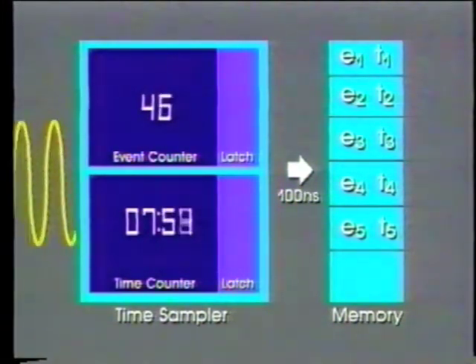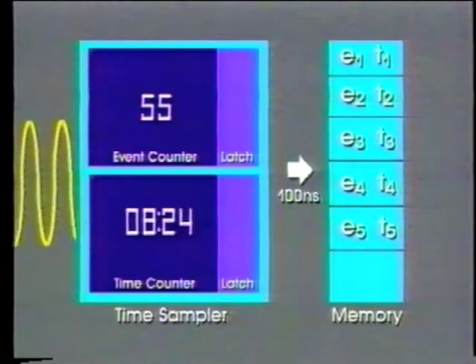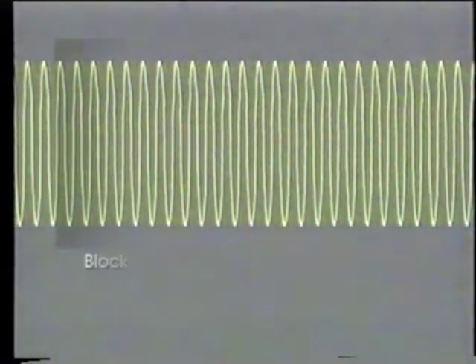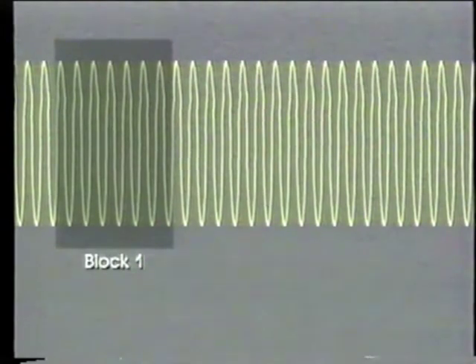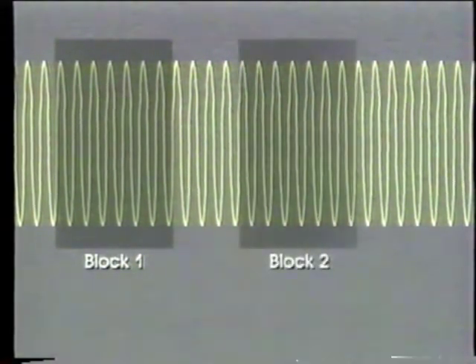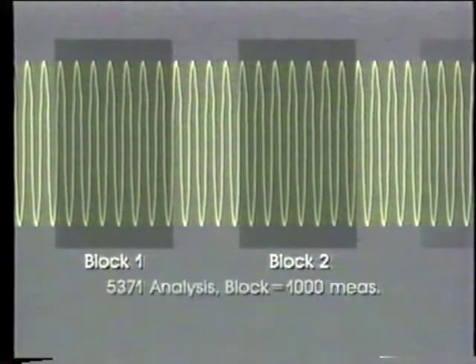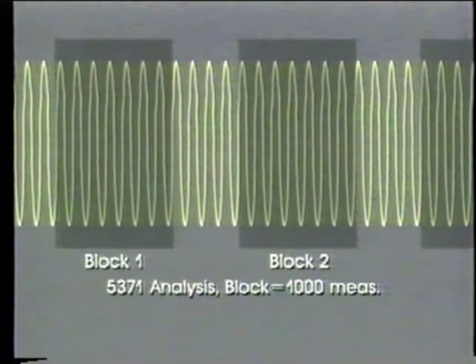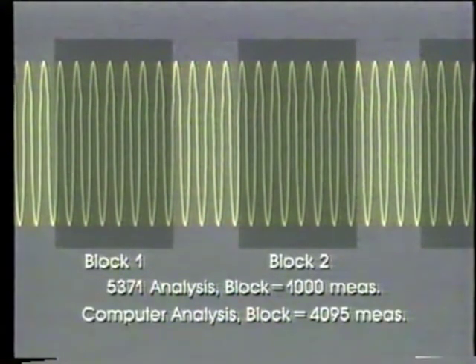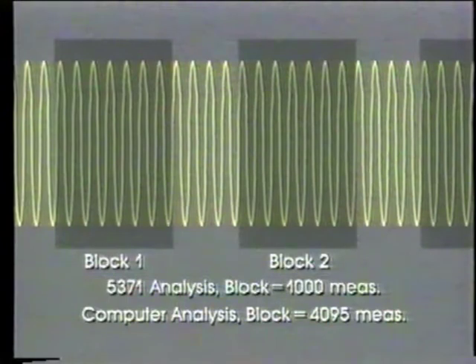The 5371 gathers event and time data in this way until an entire measurement block is taken, then stops and analyzes the data. A block consists of a continuous sequence of measurements — up to 1,000 when using the 5371 alone, and up to 4,095 when using a computer to analyze the data.